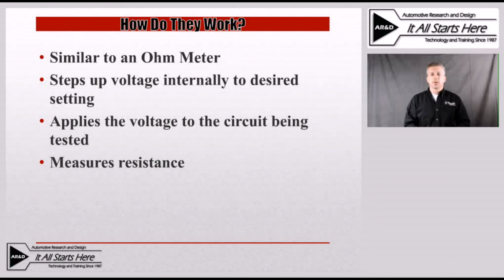So how does an insulation tester work? If you've used an ohm meter, you're already fairly familiar with it, since they operate very similarly. It takes the available voltage from the tester, generally supplied by AA batteries, and steps it up to whatever voltage you've programmed. In the light-duty automotive market right now, we typically see 250 volt and 500 volt test ranges needed for various components on different vehicle makes and models.